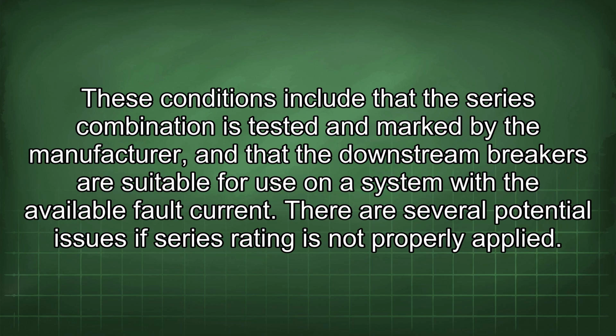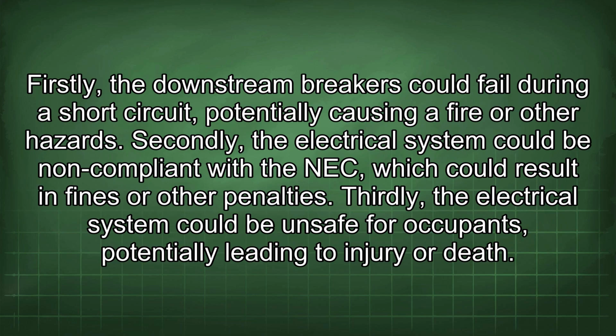There are several potential issues if series rating is not properly applied. Firstly, the downstream breakers could fail during a short circuit, potentially causing a fire or other hazards. Secondly, the electrical system could be non-compliant with the NEC, which could result in fines or other penalties. Thirdly, the electrical system could be unsafe for occupants, potentially leading to injury or death.